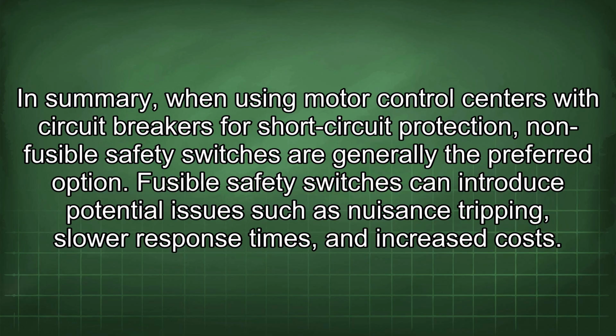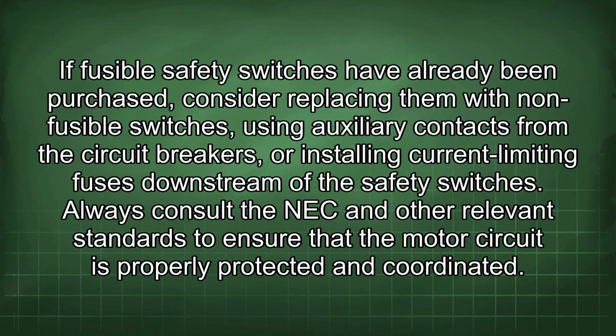generally the preferred option. Fusible safety switches can introduce potential issues such as nuisance tripping, slower response times, and increased costs. If fusible safety switches have already been purchased, consider replacing them with non-fusible switches, using auxiliary contacts from the circuit breakers, or installing current limiting fuses downstream of the safety switches. Always consult the NEC and other relevant standards to ensure that the motor circuit is properly protected and coordinated.